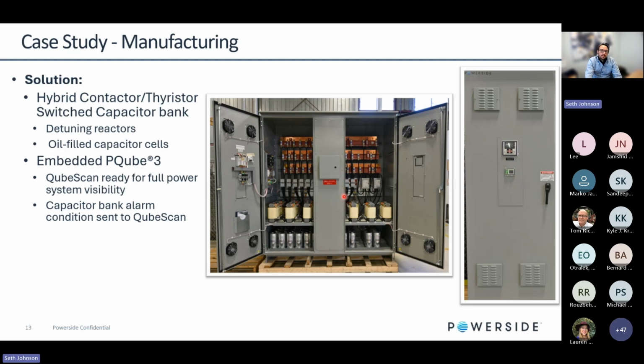As soon as that pressing operation happens, these thyristor switches over here on the right are going to engage and disengage extremely quickly. This happens in about 3 cycles. It can turn on and off. One of the reasons you can't do that with your typical contactor switch is because you're basically limited to a minimum of a 60-second delay between turning off a contactor switch stage and turning one back on again. That's because you have to let these capacitor cells discharge below 50 volts before you bring it back on.